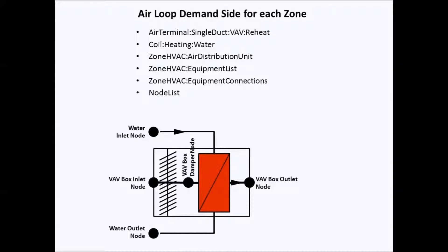This is a diagram of a VAV showing how air flows inside it. This is a reheat VAV, meaning there is a heating coil inside the VAV as well as in the AHU. Air enters into the VAV through a VAV box inlet node, then there is a damper which controls the volume of air flowing through. The volume of air flowing actually decides the temperature inside the zones — it controls volume rather than directly increasing or decreasing temperature.